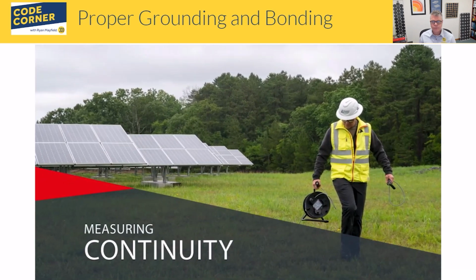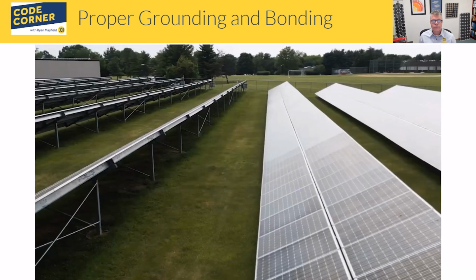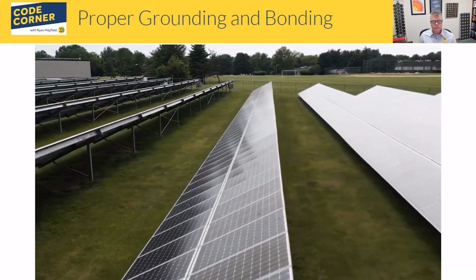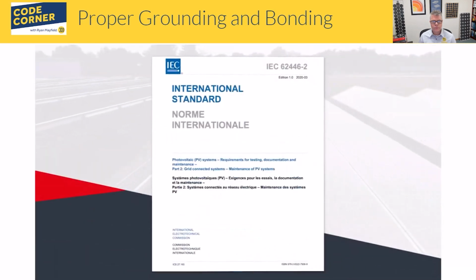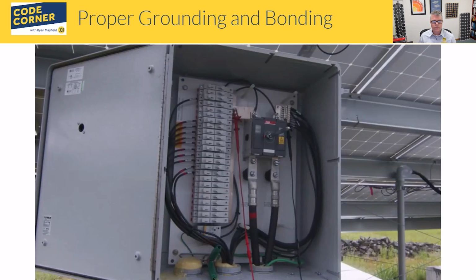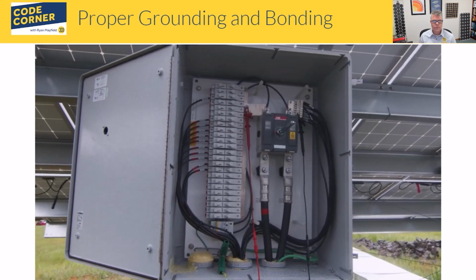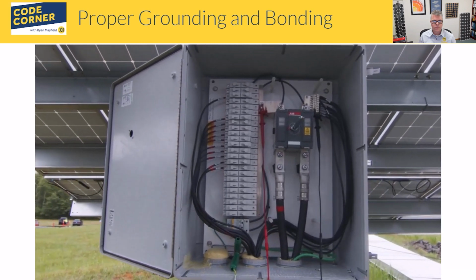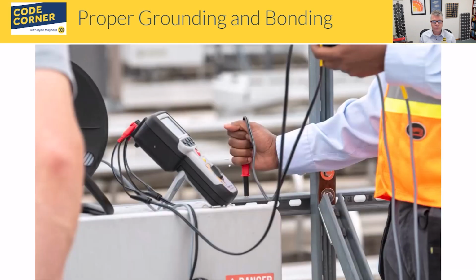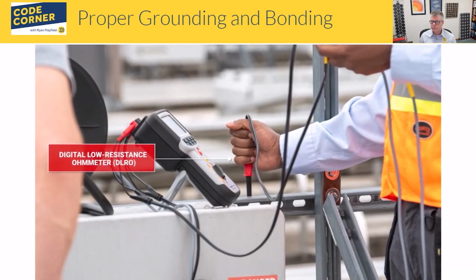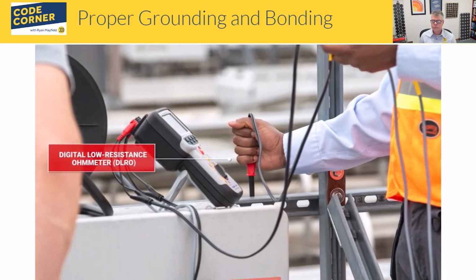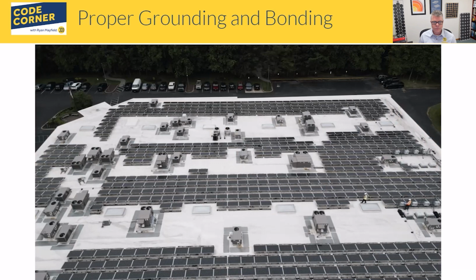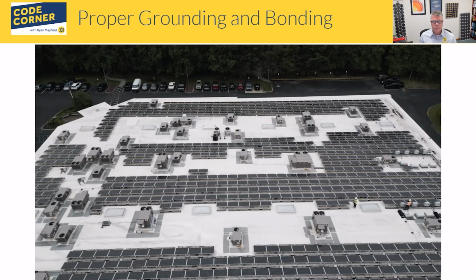Measuring continuity is an important part of the commissioning and O&M protocols for PV systems required by the IEC 62446 standard. Prior to commissioning and turning on the system, the technician must verify all metal components are electrically bonded. The use of a digital low resistance ohm meter, or DLRO, is a fast and effective way to measure continuity between all non-current carrying metal surfaces.